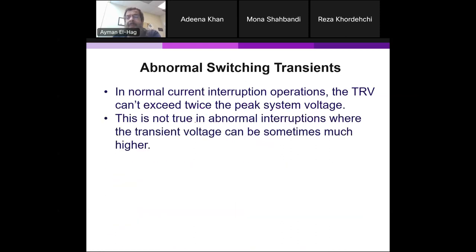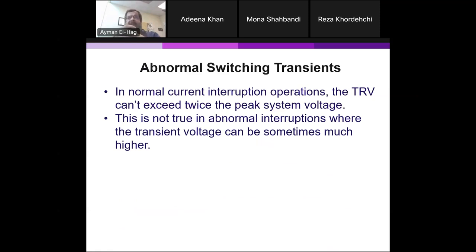For normal interruption, the transient recovery voltage cannot exceed twice the peak system voltage level. When we have abnormal interruptions in the power system, the voltages can go to much higher levels. One difference between lightning and switching is that lightning does not depend on the voltage level of the system — whether it hits a distribution or transmission system, the amount of overvoltage doesn't depend on the voltage level. Most switching events, on the other hand, do depend on voltage level. But there are certain types of switching that do not depend on the system voltage level.